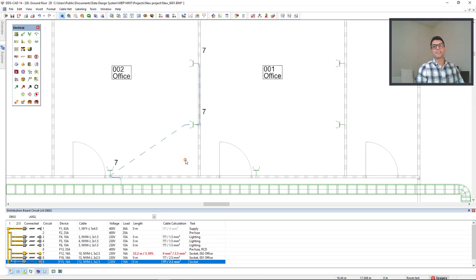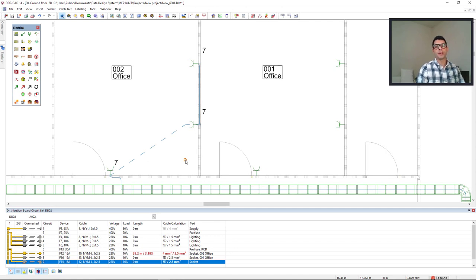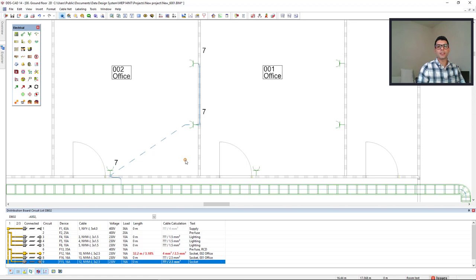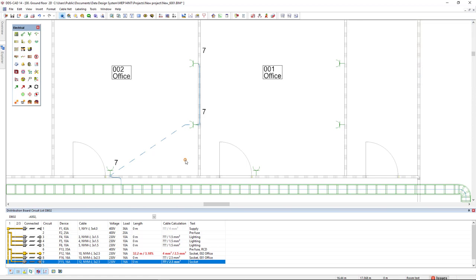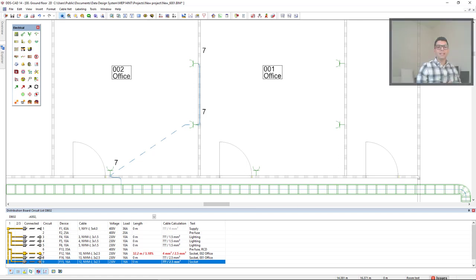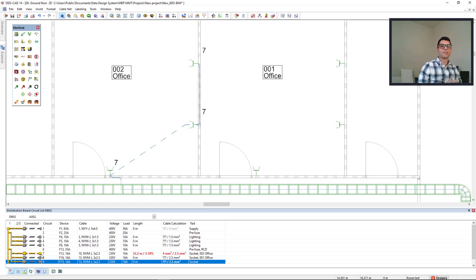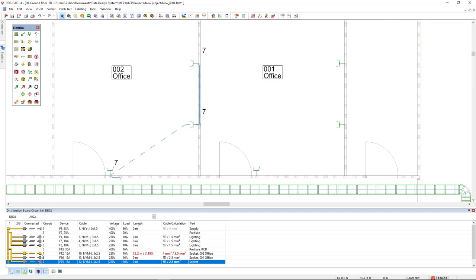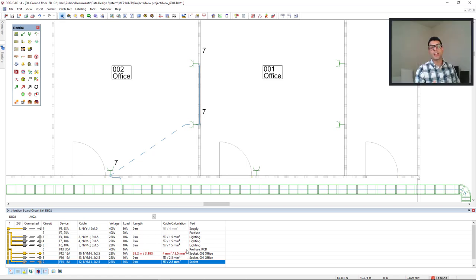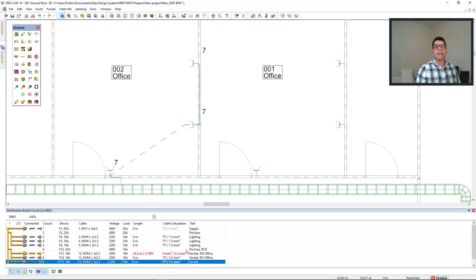In the room office number two, I have drawn the cable to connect to these three sockets, creating the circuit number seven. In the distribution board circuit list, we see in a connected column the indication in yellow, meaning the cable is correctly connected from the board to the objects. However, we see in the length and in the cable calculation columns the values highlighted in red, meaning these values exceed the limits.